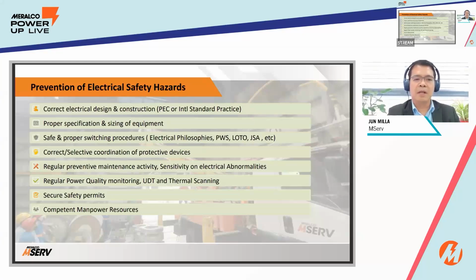Fourth, correct selective coordination and protective devices. In our system, particularly in our house, the main circuit breaker should not trip or operate if there's a fault downstream. So meaning, if you have a fault on your power socket outlet and there's a problem in the equipment that you plug in, there is a corresponding breaker that protects that equipment, not the main circuit breaker.